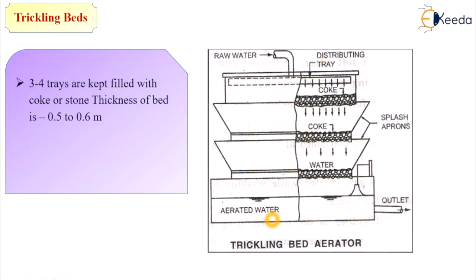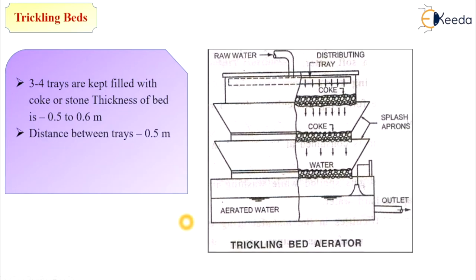Aerated water is collected from the outlet, and the biological sludge formation is removed by drains. The system consists of 3 to 4 trays filled with coke, stone, or filter media, with a bed thickness of approximately 0.5 to 0.6 meters. The distance between trays is 0.5 meters and water is sprayed from a distribution pipe at the top.